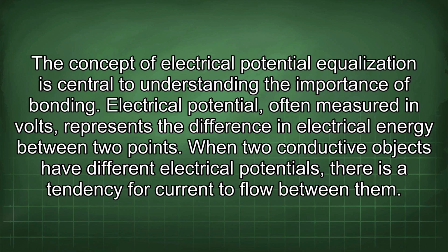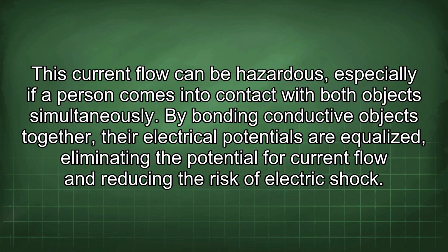Electrical potential, often measured in volts, represents the difference in electrical energy between 2 points. When two conductive objects have different electrical potentials, there is a tendency for current to flow between them. This current flow can be hazardous, especially if a person comes into contact with both objects simultaneously.